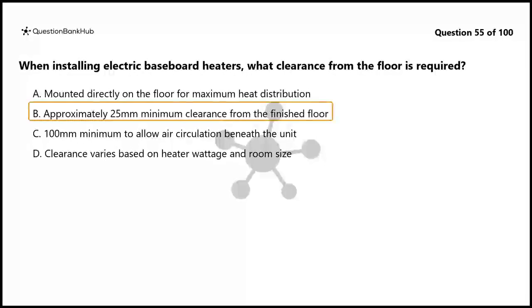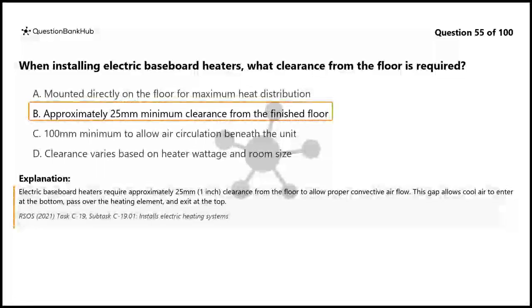The correct answer is B. Approximately 25 mm minimum clearance from the finished floor. Electric baseboard heaters require approximately 25 mm, 1 inch, clearance from the floor to allow proper convective air flow. This gap allows cool air to enter at the bottom, pass over the heating element, and exit at the top.